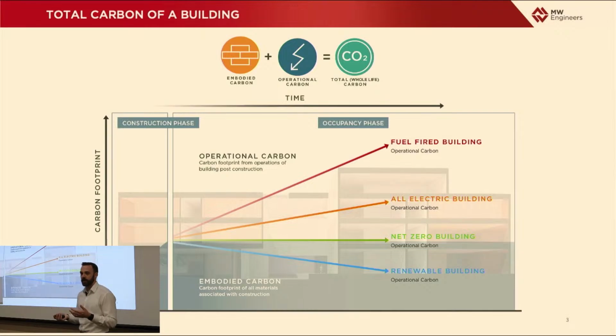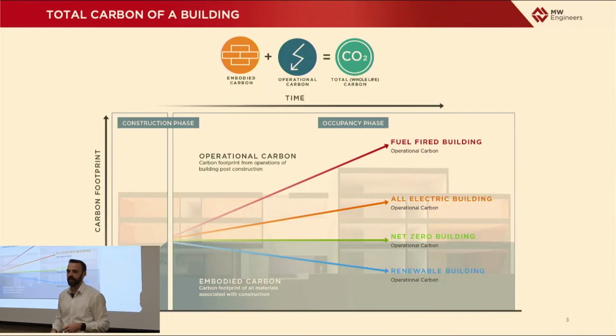Think of your house maybe: you've got a gas-fired furnace, and every time you turn it on, it burns gas to heat your house. That's very true of buildings like this on campus. When we need to heat buildings connected to the steam plant, you have to turn on those steam boilers and create steam. That steam is distributed to the buildings, and there are losses associated with that distribution which reduce efficiency. That's what this fuel-fired building line represents — using fossil fuels to actually heat and operate your building.